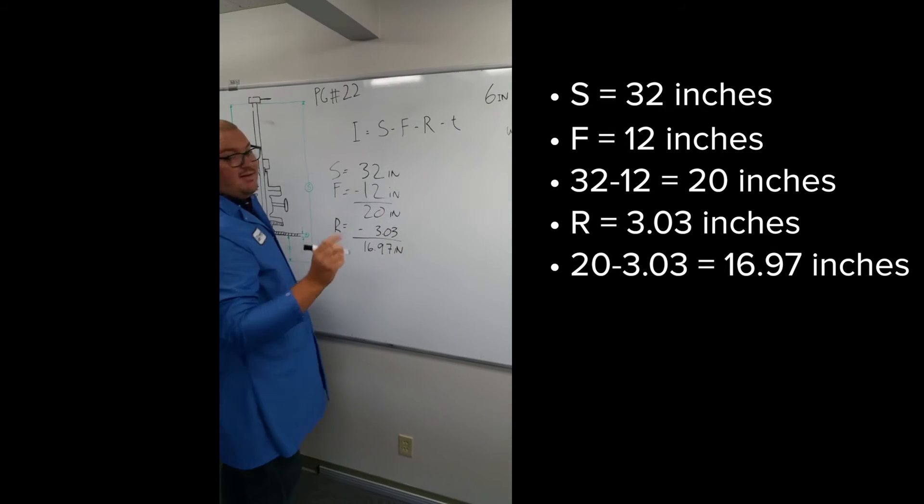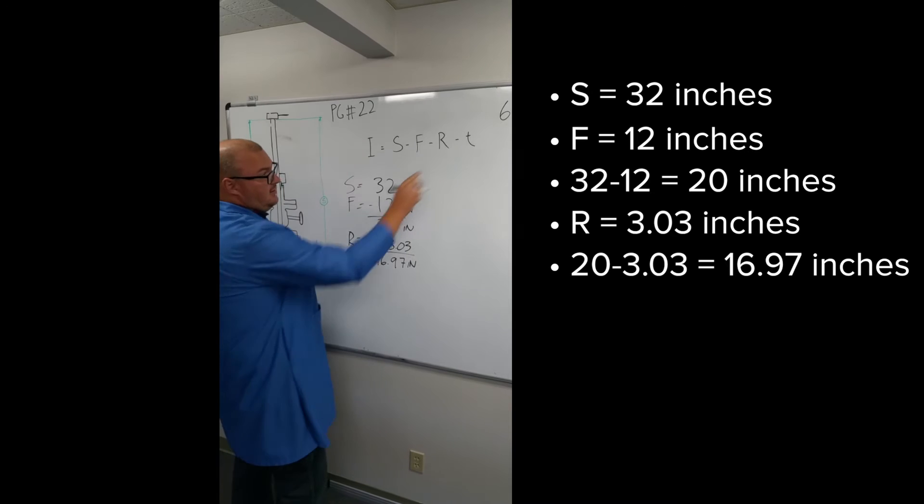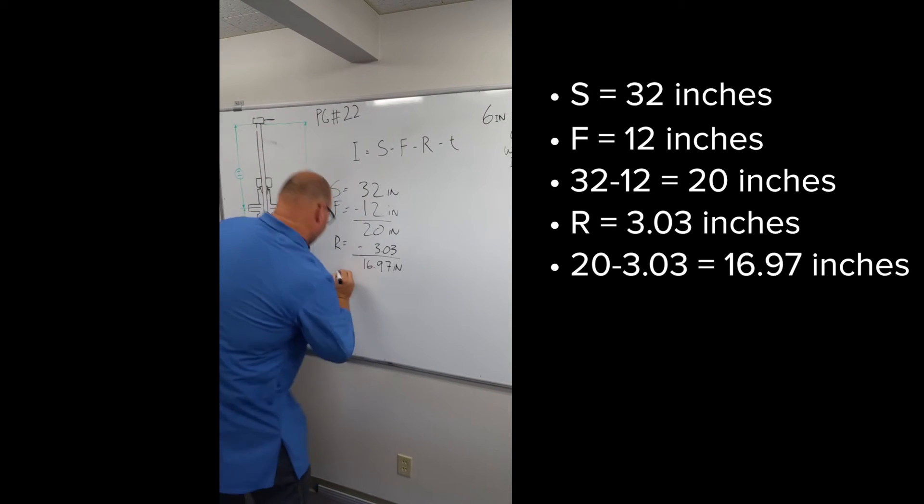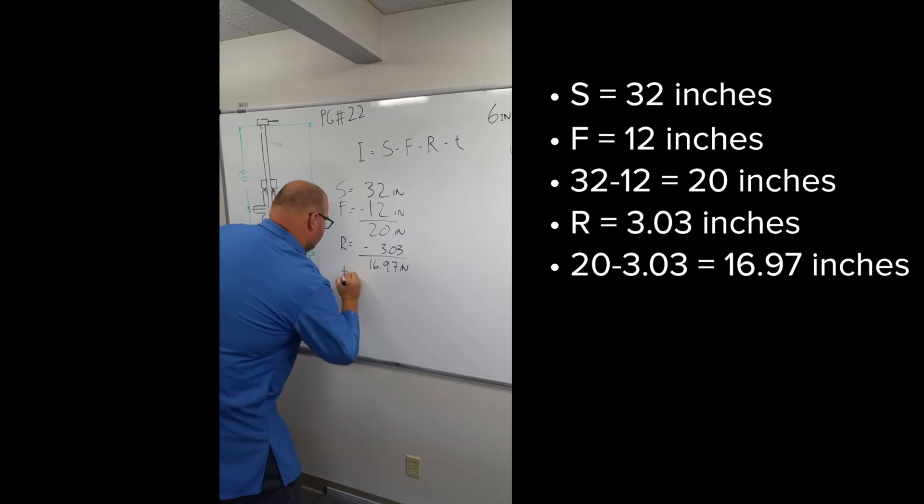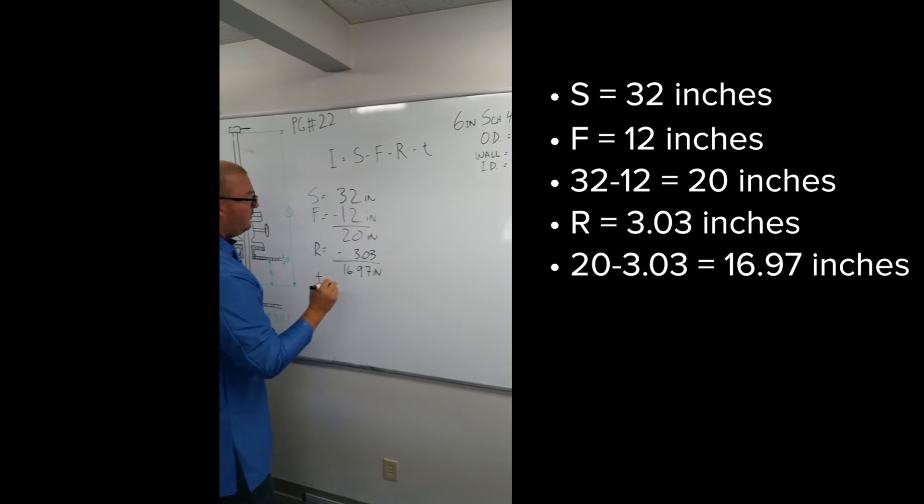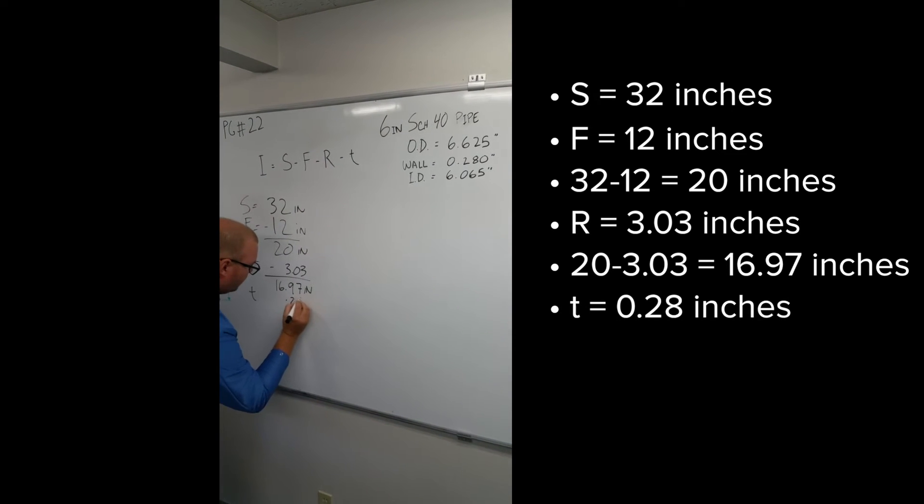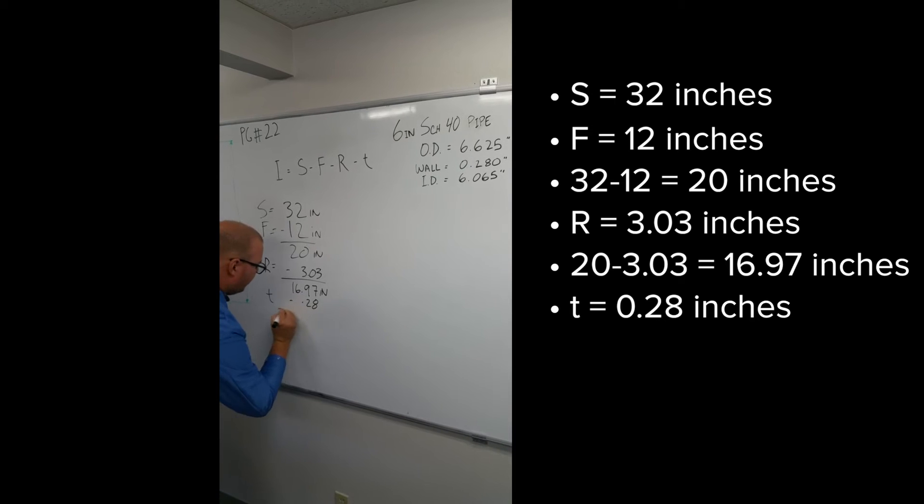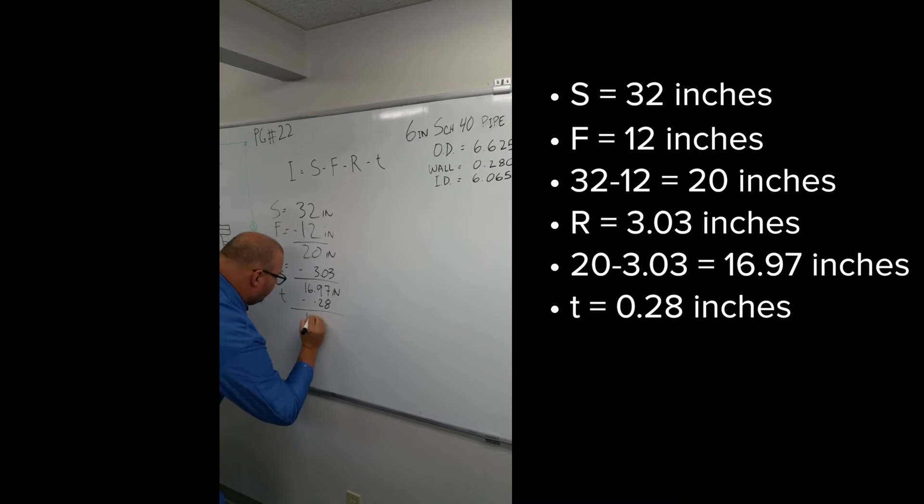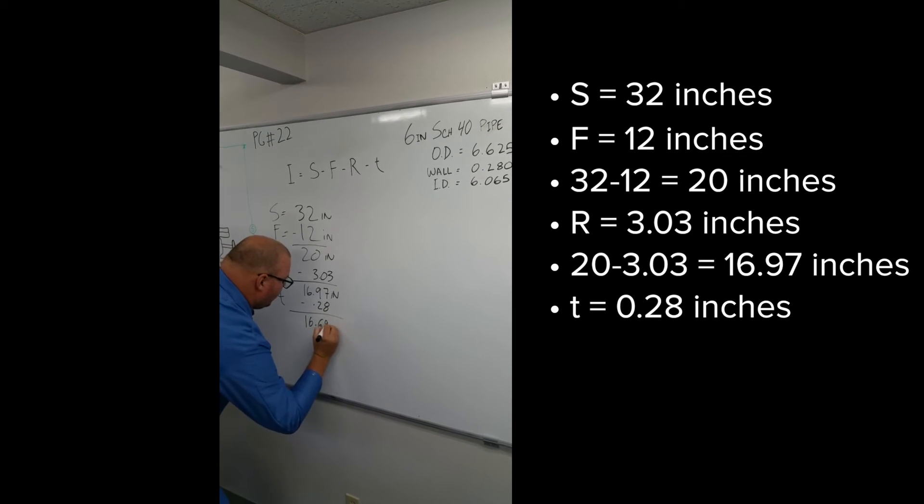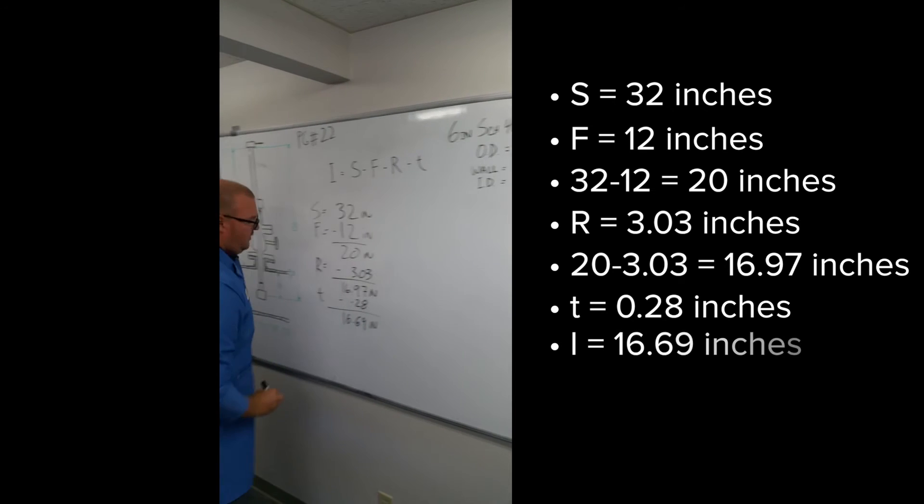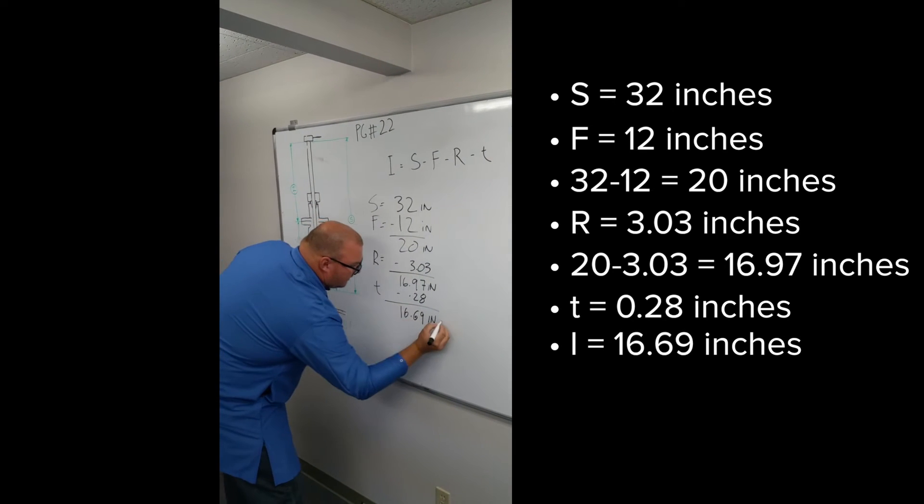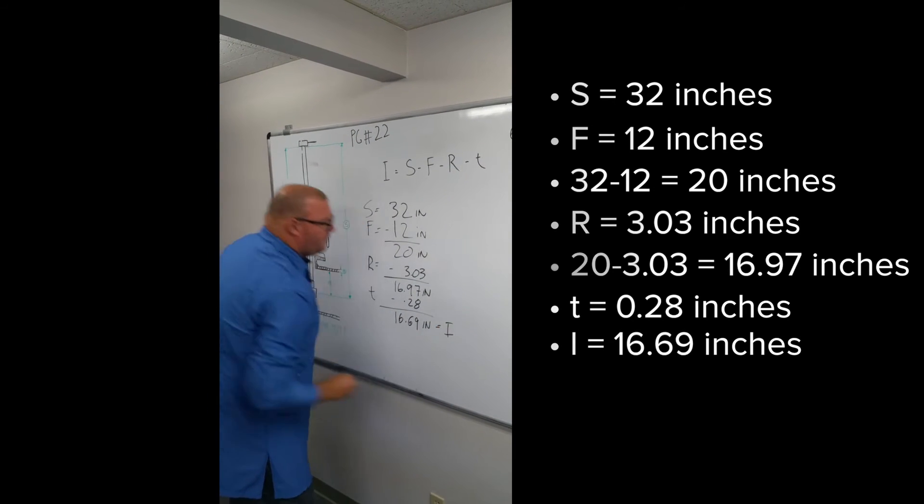We're almost finished. The last thing we need to do for our formula is subtract the wall thickness. T is equal to .280. Subtract that and we're left with 16.69 inches. And that is what I equals. That's our insertion depth.